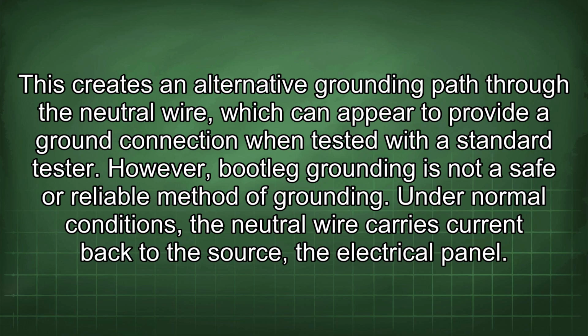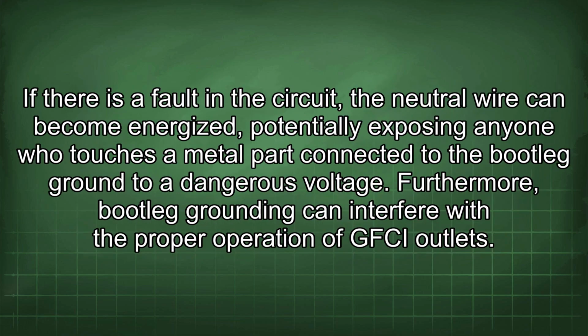Under normal conditions, the neutral wire carries current back to the source, the electrical panel. If there is a fault in the circuit, the neutral wire can become energized, potentially exposing anyone who touches a metal part connected to the bootleg ground to a dangerous voltage. Furthermore, bootleg grounding can interfere with the proper operation of GFCI outlets.